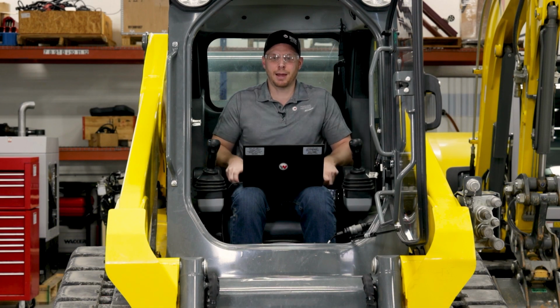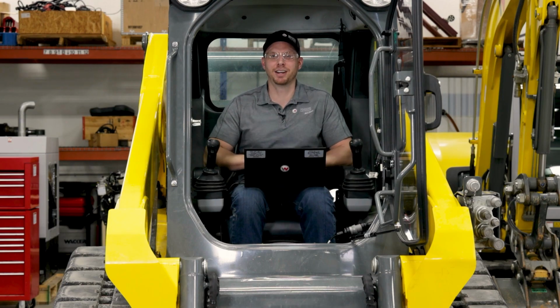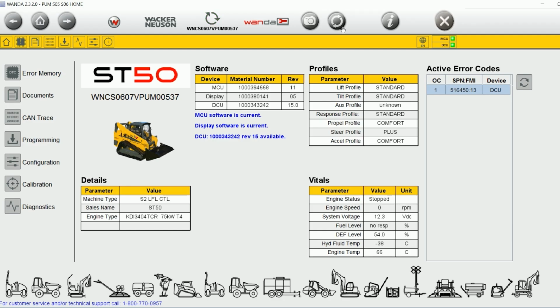To begin the pump calibration procedure, you're going to want to grab your laptop, your Wanda cable, and establish connection and connect to the machine. So I have already connected to the machine, I'm connected to my laptop, and you now have to launch the software. When you have established connection with Wanda to the machine, you're going to navigate to the calibration page.